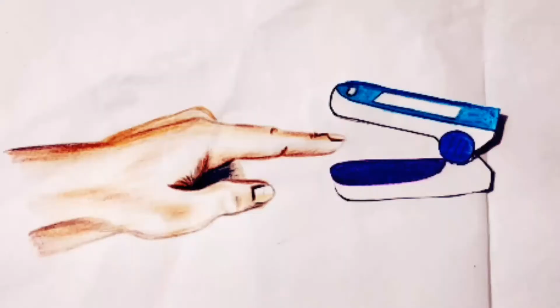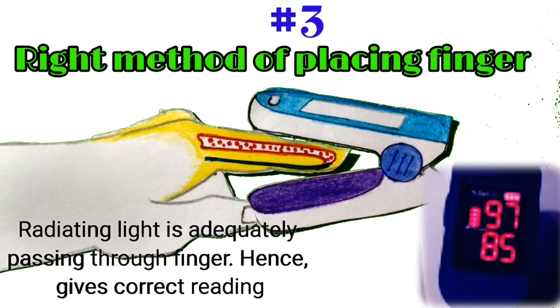Let us have a look into the correct method of placing the finger in the oximeter. In this first method, the radiation source is not at all passing through the finger, hence no reading on the LED screen. This second method is also a wrong method of placing the finger. In this, the radiation light is not adequately passing through the finger, hence gives a false reading. So this is the right method of placing the finger. Here the radiation light is passing through the finger, hence gives a correct reading.